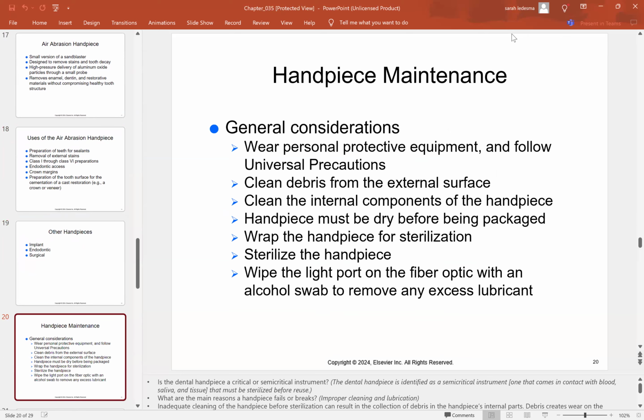Handpiece maintenance, general considerations: wear personal protective equipment and follow universal precautions. Clean debris from the external surface. Clean the internal components of the handpiece. The handpiece must be dry before being packaged. Wrap the handpiece for sterilization. Sterilize the handpiece. Wipe the light port on the fiber optic with an alcohol swab to remove any excess lubricant.